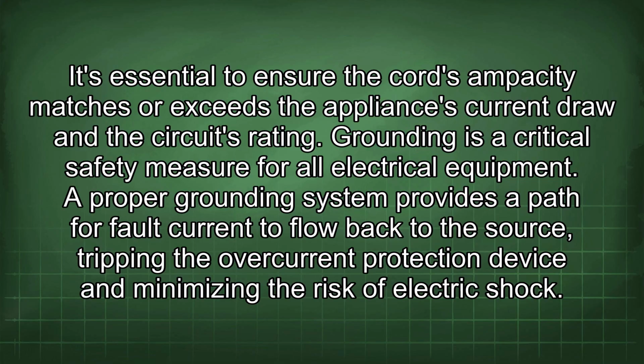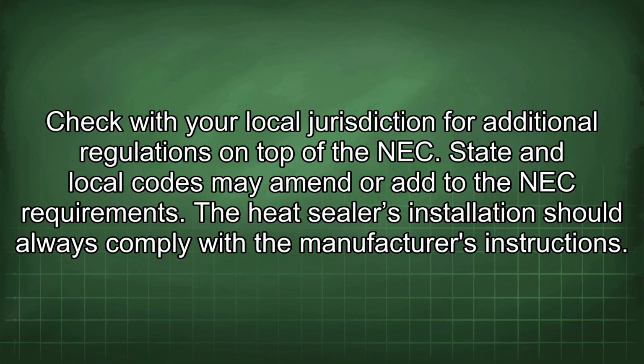Grounding is a critical safety measure for all electrical equipment. A proper grounding system provides a path for fault current to flow back to the source, tripping the overcurrent protection device and minimizing the risk of electric shock. Check with your local jurisdiction for additional regulations on top of the NEC. State and local codes may amend or add to the NEC requirements.